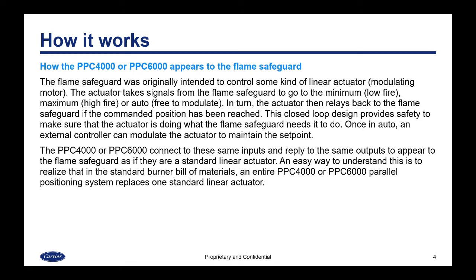The closed loop design provides safety to make sure that the actuator is doing what the flame safeguard needs it to do. Once in auto, an external controller, such as a PID controller, can modulate the actuator to maintain the set point. The PPC4000 or PPC6000 connect to these same inputs and reply to the same outputs to appear to the flame safeguard as if they are a standard linear actuator. An easy way to understand this is to realize that in a standard burner bill of materials, an entire PPC4000 or PPC6000 parallel positioning system really just replaces one standard linear actuator.